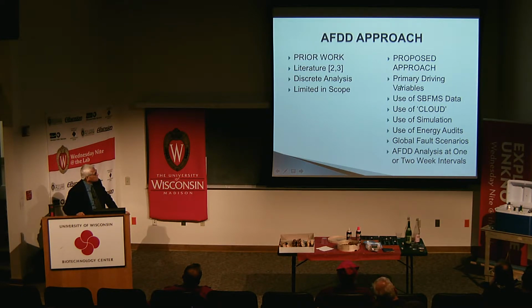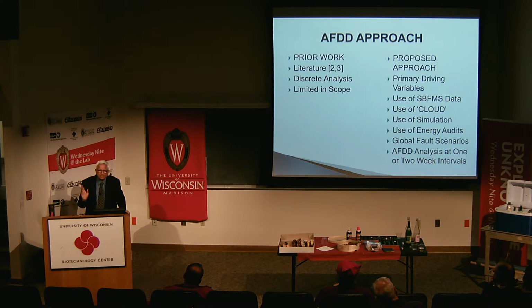Another important thing I did was to ask what drives the fault. If you take the whole building, what drives the fault? I said we should consider three primary variables. One is temperature in the occupied zone. One is CO2 level in the occupied zone, because of the CO2 generated by occupants; we have to keep it at a certain optimal level according to the standards. Third is metered energy consumption. I will come to that a little later.